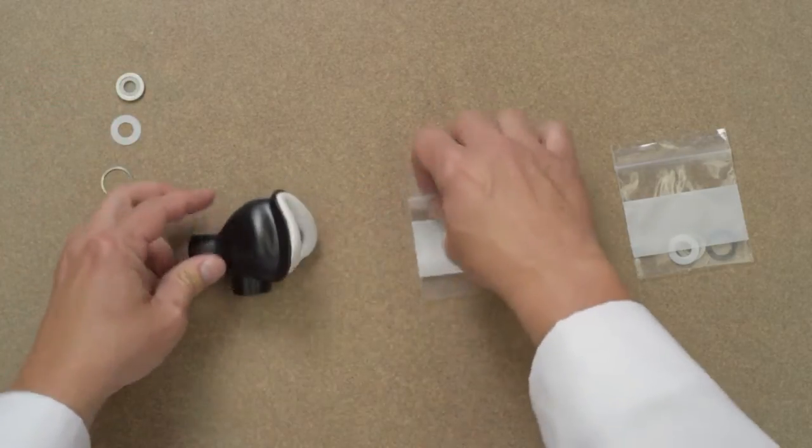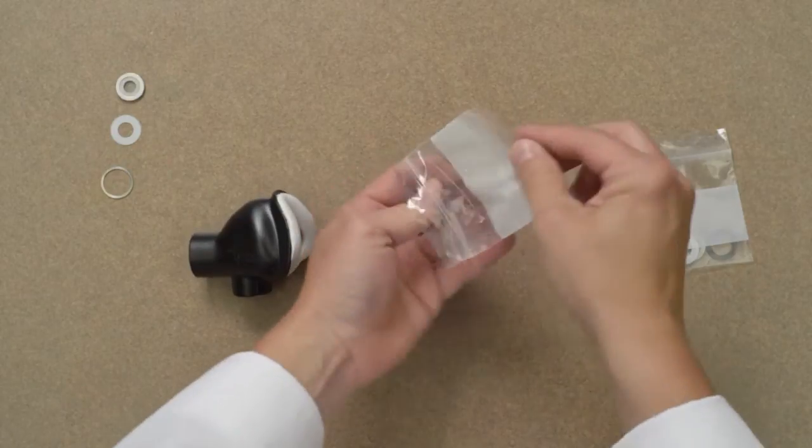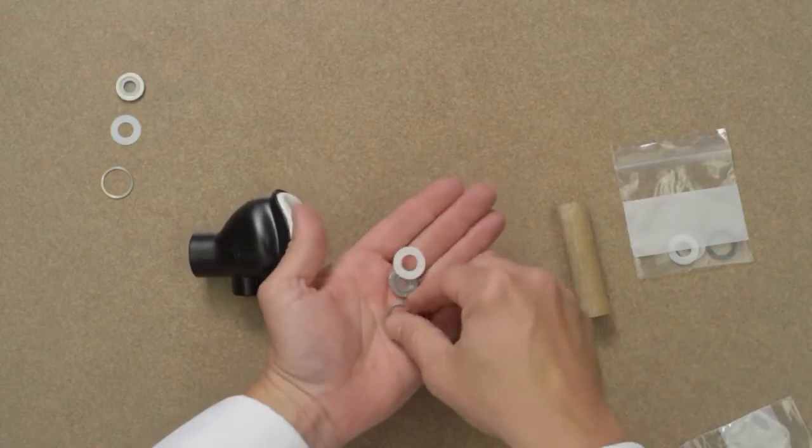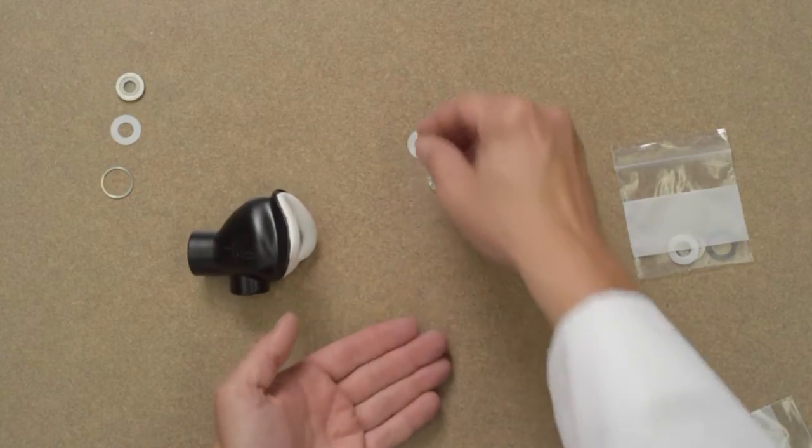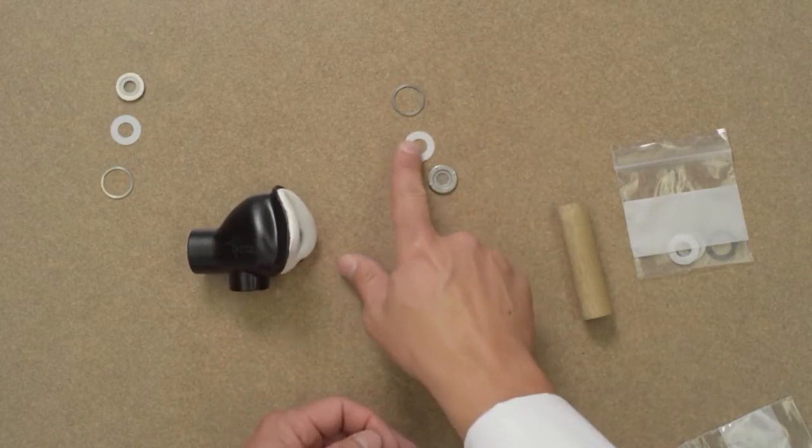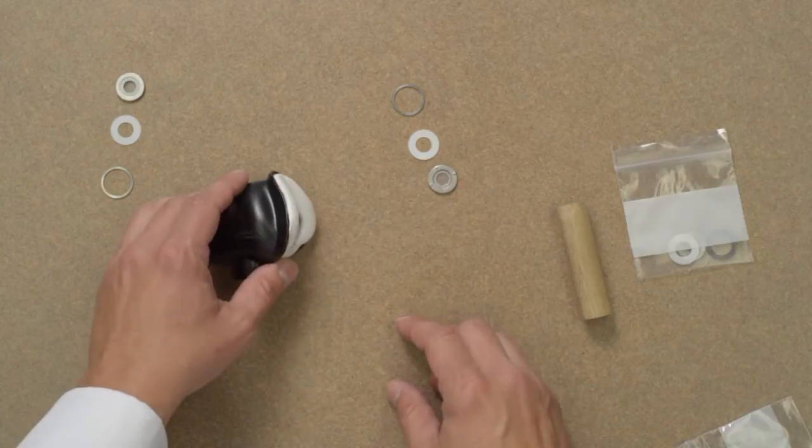Next lay out the parts for the new inhale check valve. We have three parts for the inhale check valve: the check valve body, a Teflon washer, and a retainer spring washer. These parts should be inserted into the inhale port in this order.